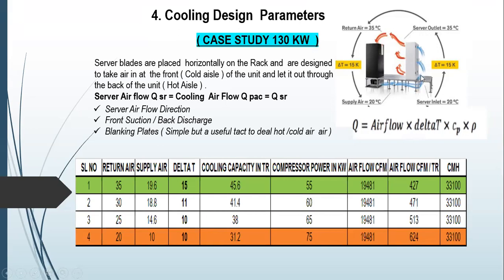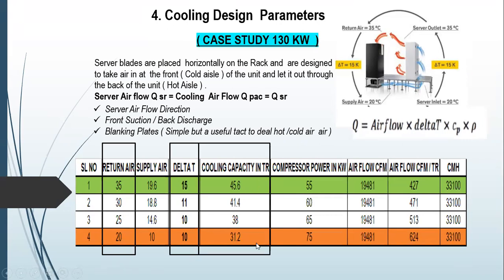And here you could see a bottom throw, the blue color denominates the cold air and the red color is the hot air. A quick case study here from an extreme return air, as I talked about in the previous slide, return air of 20 to a return air of 35. As I said, the higher the delta T, the better it is, in terms of there is an increase in the cooling capacity, there is a decrease in the power consumption from these units.